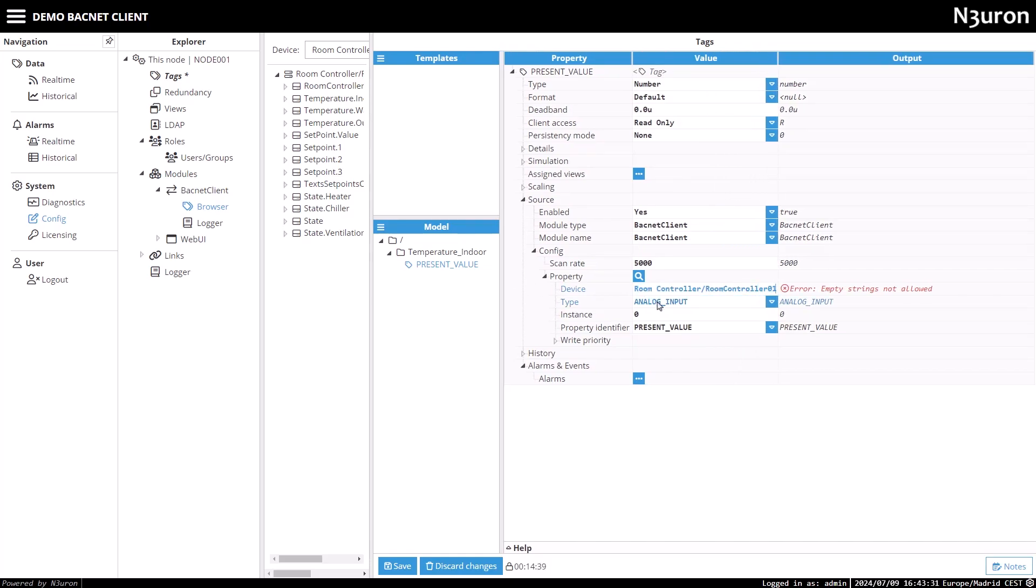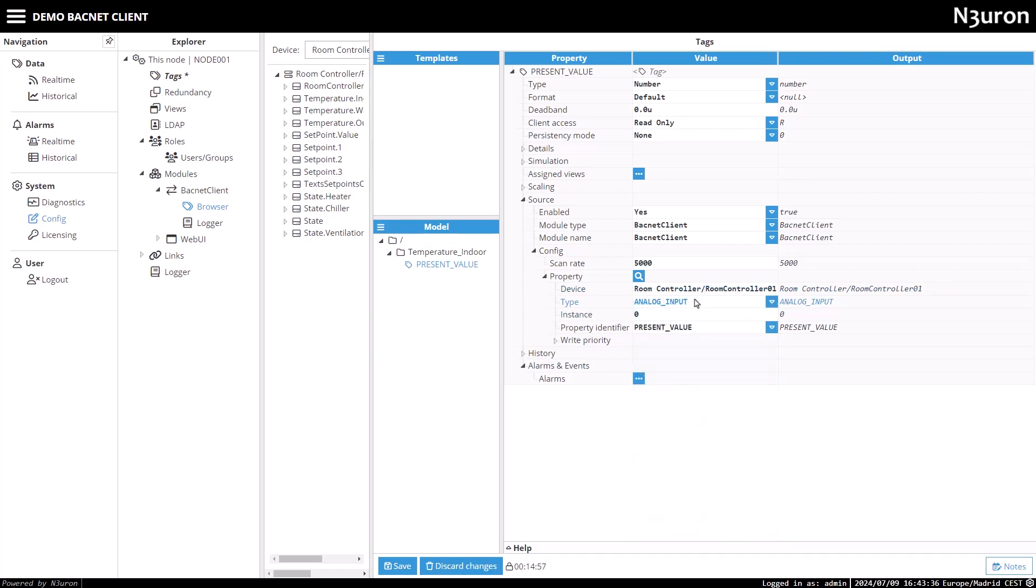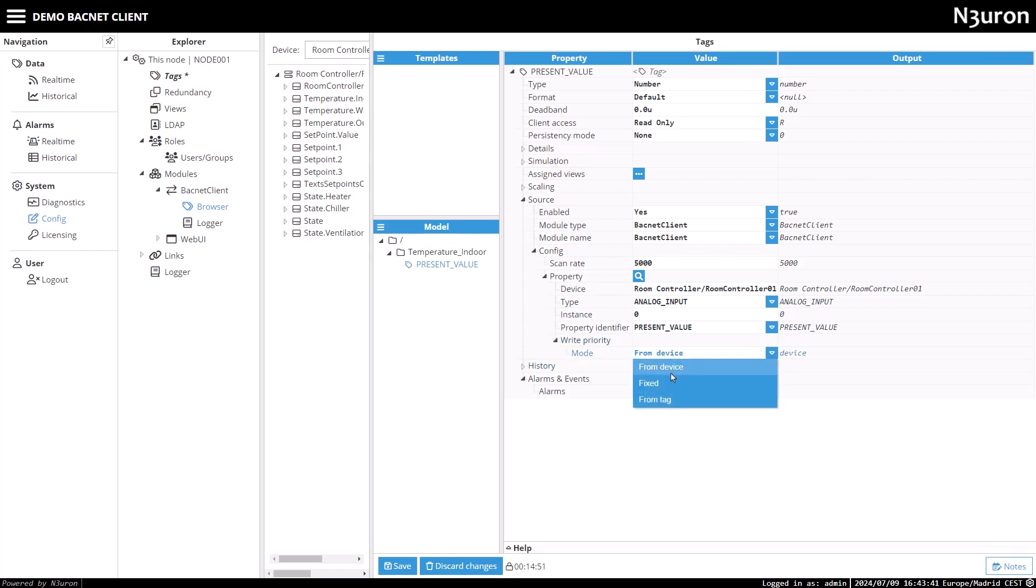For the type, I'll select analog input as the object type. The instance or object instance will be set to zero, and the property identifier will be set to present value. I'll also choose from device as the write priority.